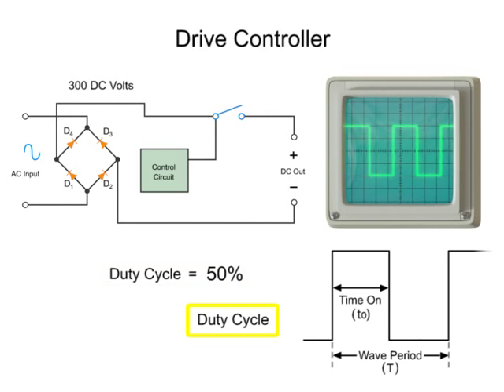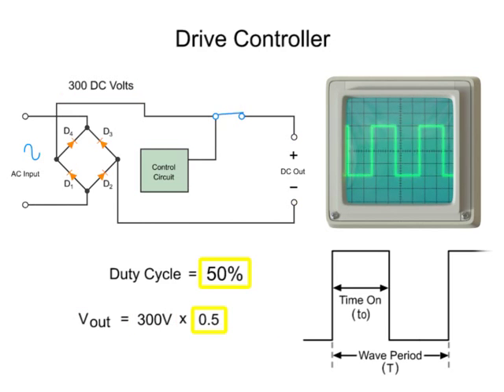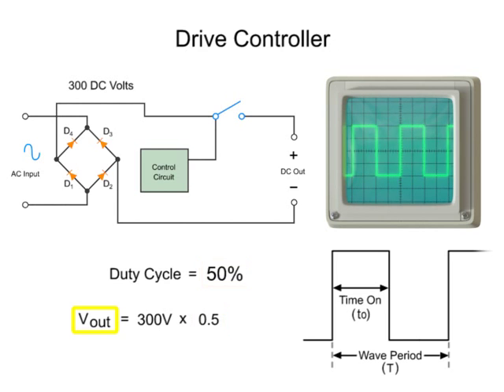Multiplying the duty cycle times the input voltage will give you the voltage output. In this example, a 300 volt input will be modulated by 50 percent, so the final voltage delivered to the load, or motor, is 150 volts.